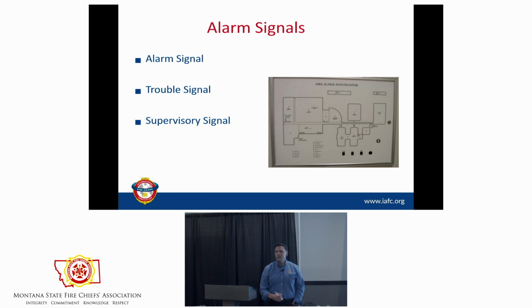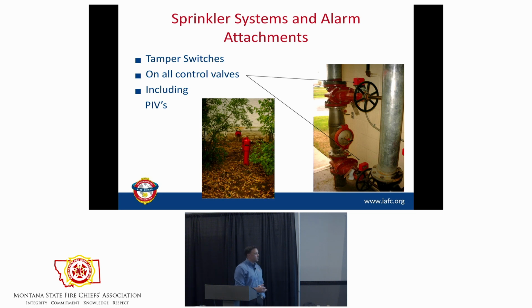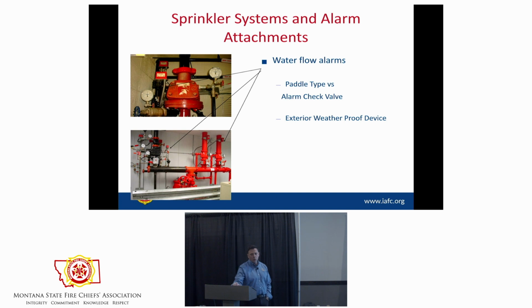Why would a sprinkler system be closed? Maintenance, testing, arson. Okay? And so we may change. For instance, in our orders of operation, our first-in engine goes to what's best for fighting fire. Our second engine goes to the FDC. That's the way we do it. I know other departments that flip it, right? And you may have to flip it based on what you know. And so we have all these attachments that are all over the place to create those, right? So those red boxes would be a supervisory signal if somebody closes that control valve, right? Our water flow devices show in different ways. If you're always responding to a water flow, what we want is our company officers to say water flow system 1, put it in your report. We responded to a false alarm. It was water flow number 1. That way our prevention folks can get on top of it, because now I can limit it. Sometimes those things go bad and they need to be replaced.